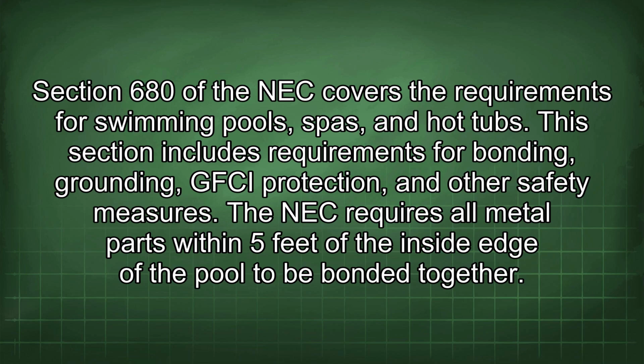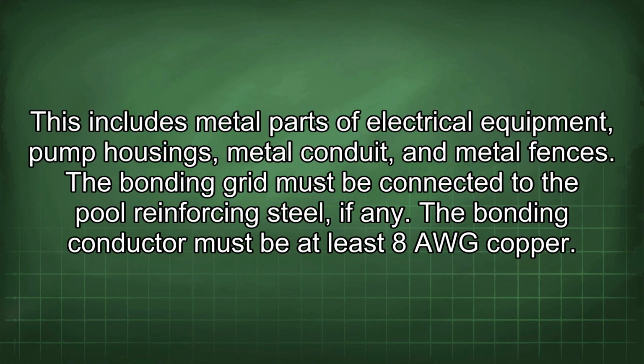The NEC requires all metal parts within 5 feet of the inside edge of the pool to be bonded together. This includes metal parts of electrical equipment, pump housings, metal conduit, and metal fences. The bonding grid must be connected to the pool reinforcing steel, if any. The bonding conductor must be at least 8 AWG copper.